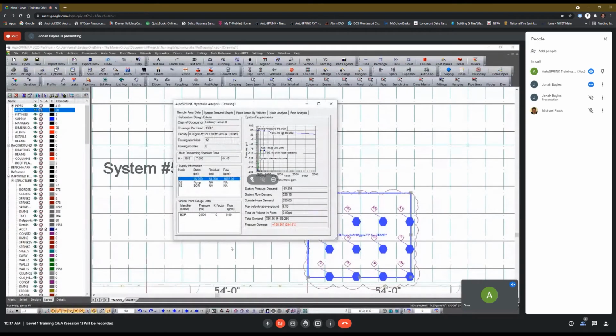Okay, so you've got these heads set to discharge a minimum 7 psi. So you've got 16.8K heads discharging a minimum 7 psi, which equals 44.45 GPM each. That minimum 7 psi is probably not appropriate.